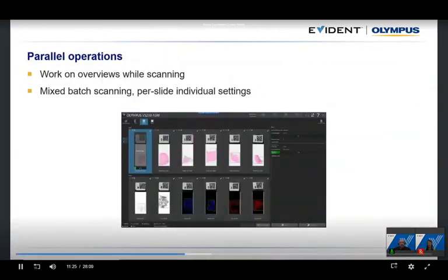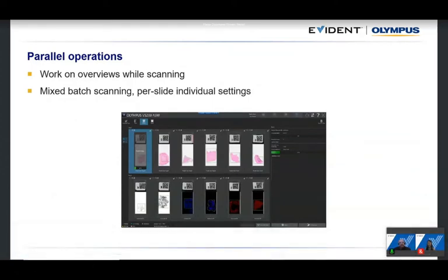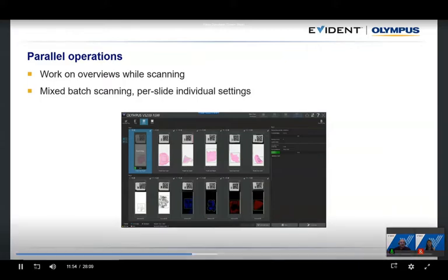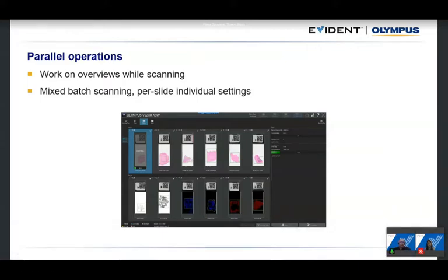The system supports parallel operation: once overviews are acquired you can start defining what to scan while the system continues acquiring other overviews. Mixed batch scanning is also supported — in the autoloader you can have slides of different sizes, each assigned a completely different acquisition protocol. Once defined, you press start scan and the system automatically produces all the scans you need.